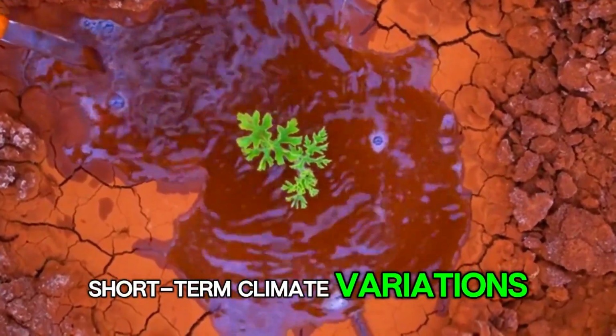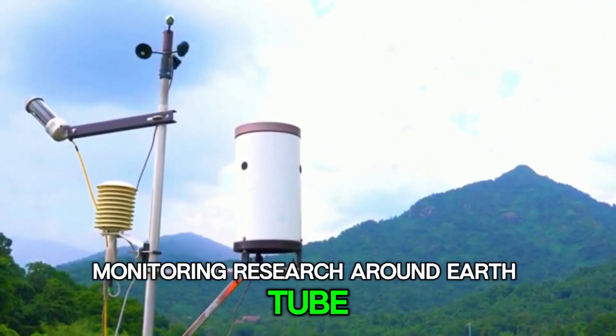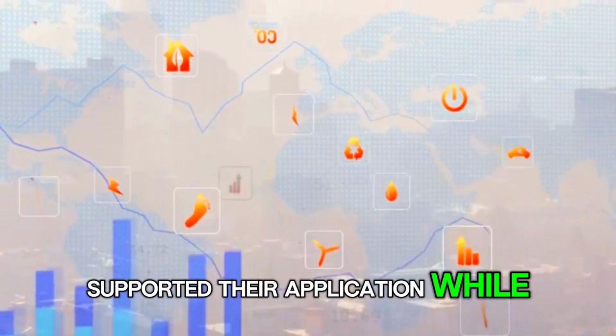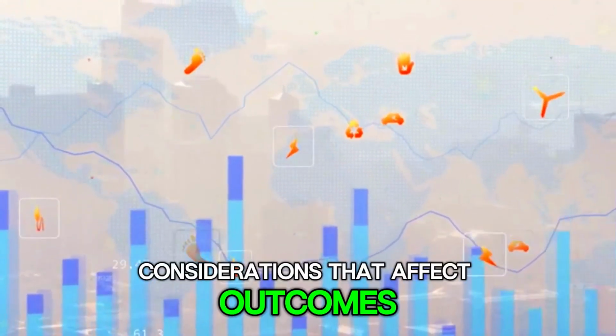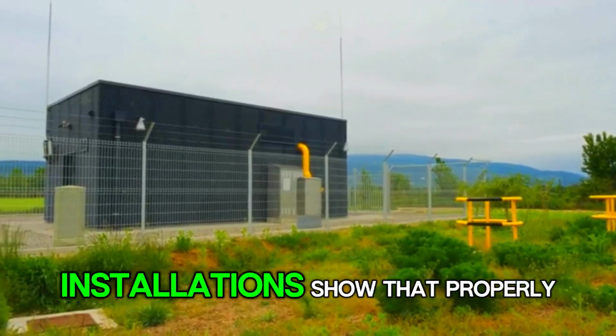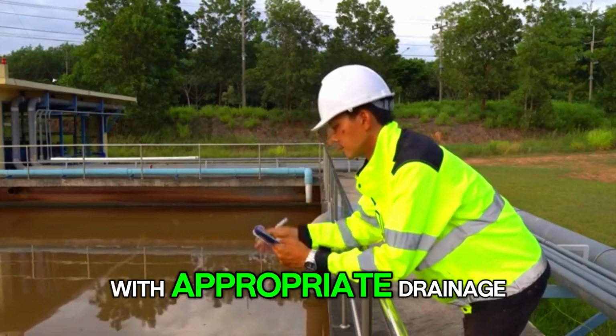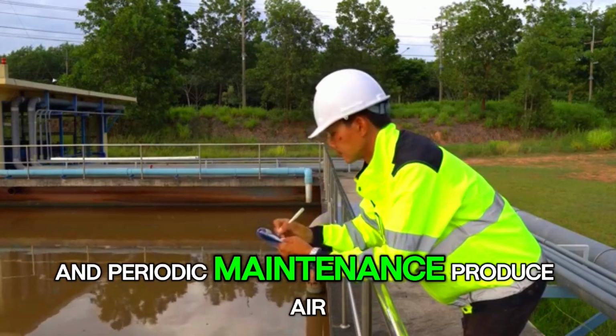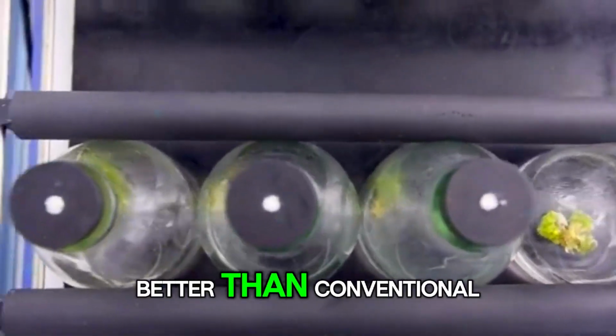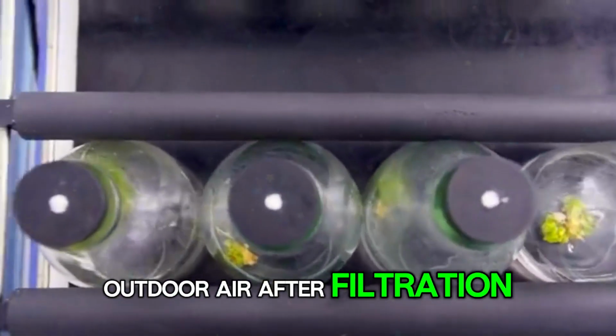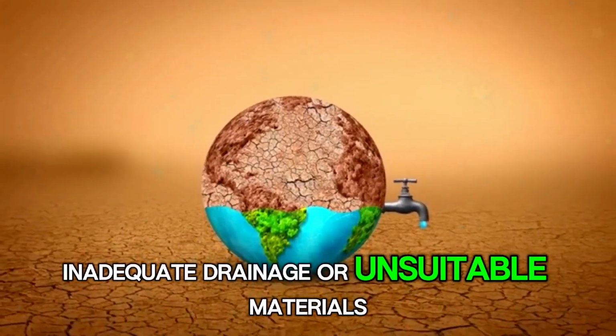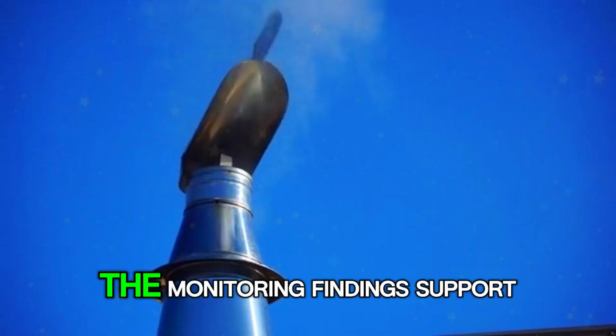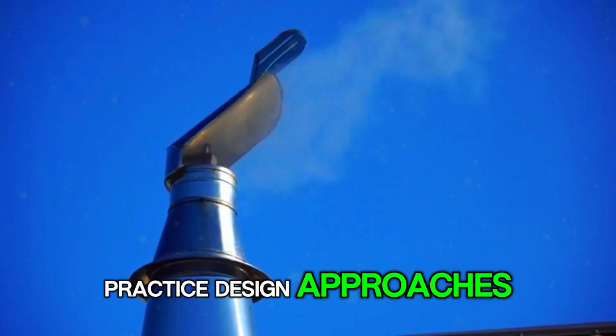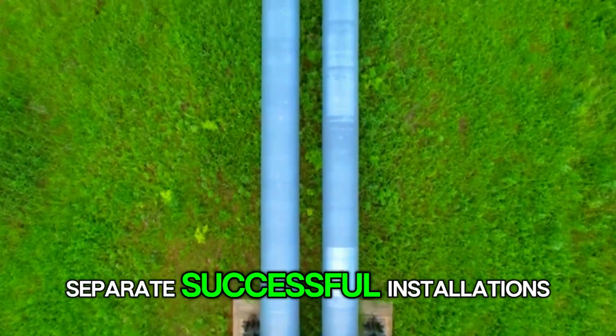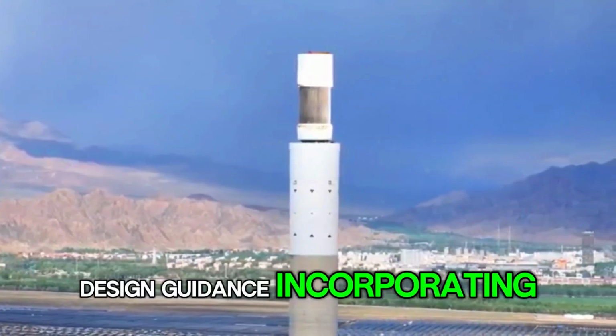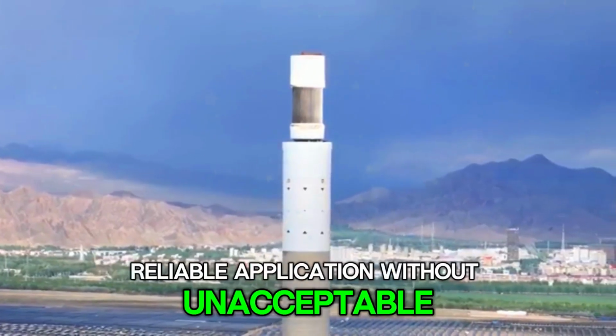Air quality monitoring research around earth tube installations has generally supported their application while identifying specific design considerations that affect outcomes. Long-term monitoring studies in European installations show that properly designed systems, with appropriate drainage, material selection, and periodic maintenance, produce air quality comparable to or better than conventional outdoor air after filtration. Poorly designed systems with inadequate drainage or unsuitable materials can create air quality problems. The monitoring findings support adoption of best practice design approaches while identifying the specific factors that separate successful installations from problematic ones. Design guidance incorporating these findings enables reliable application without unacceptable air quality risks.